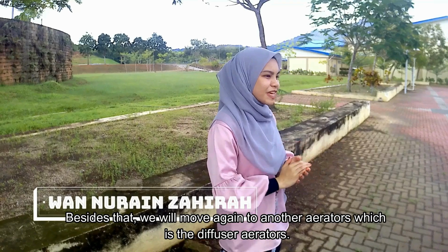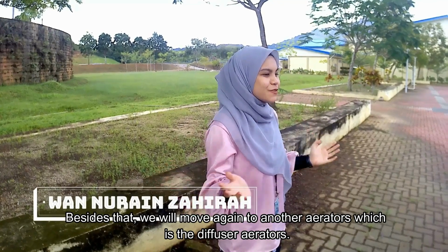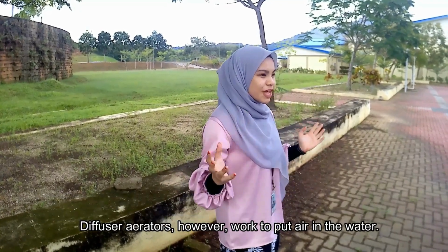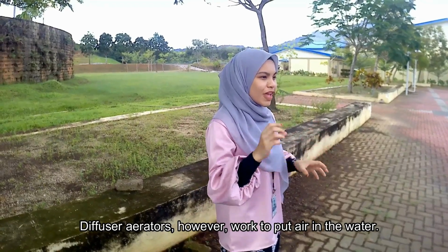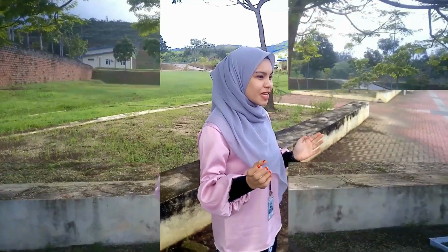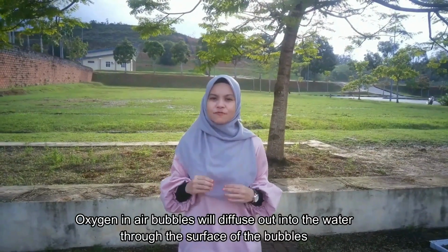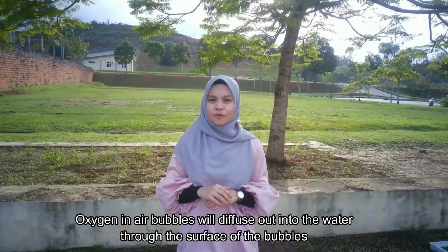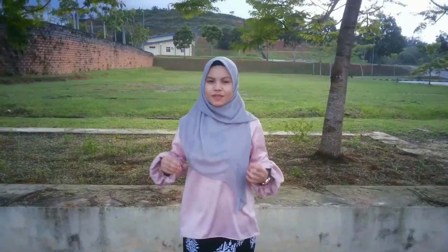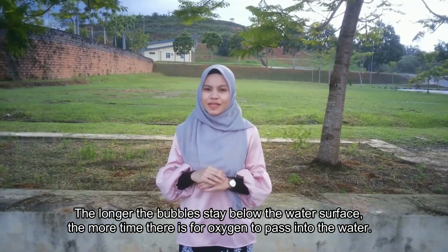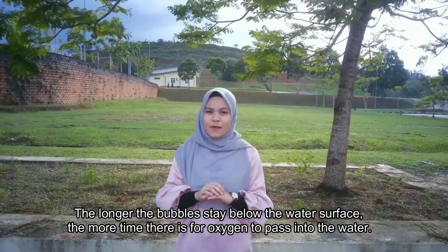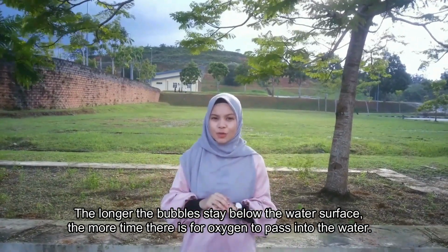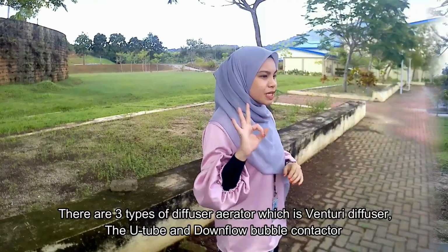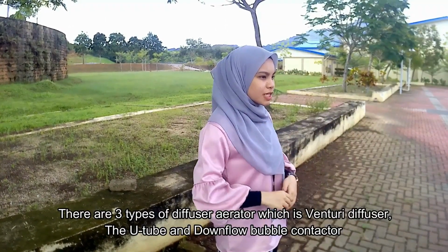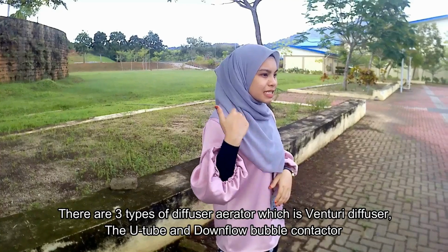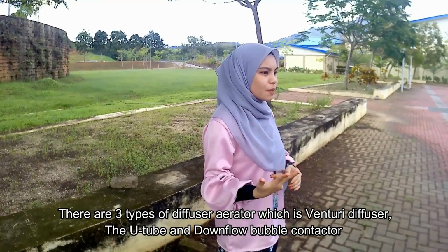Besides that, we will move again to another aerator, which is the diffuser aerator. Diffuser aerators, however, work to put air in the water. Oxygen in air bubbles will diffuse out into the water through the surface of the bubble. The longer the bubbles stay below the water surface, the more time there is for oxygen to pass into the water. There are 3 types of diffuser aerators, which are the venturi diffuser, the U-tube, and the downflow bubble contactor.